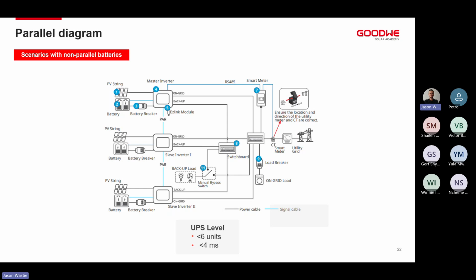The caveat to that is we need to make sure that the battery capacities are the same. So if we've got 10 kilowatt hours on battery inverter 1, we need to put 10 kilowatts on number 2 and 10 kilowatts on number 3. This is not the most ideal situation as the installer or end user, as one of the inverters may work harder than the other because the battery is obviously older, and we might not get the full output capacity.